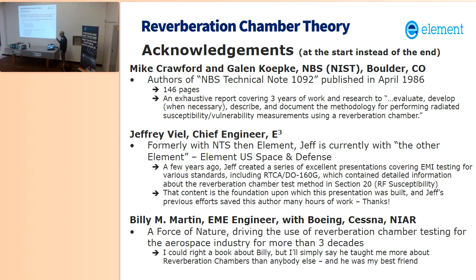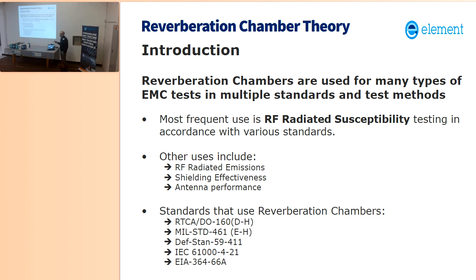Okay, so reverberation chambers are used for many types of EMC tests. So it's not just radiated susceptibility, although that's primarily what it's used for. DO-160 is probably the most frequent test. DO-160 RF radiated susceptibility in accordance with section 20.6 is probably the most frequent, but it's used for many others as well. You can run RF radiated emissions. Section 21 has a method for running radiated emissions. It's the best way to do a shielding effectiveness test, I believe. You can test all kinds of different things. We run a lot of tests for testing cables for shielding effectiveness. You can also test antenna performance. You can't get necessarily beam width, but you can get antenna efficiency, other parameters about the effectiveness of an antenna.